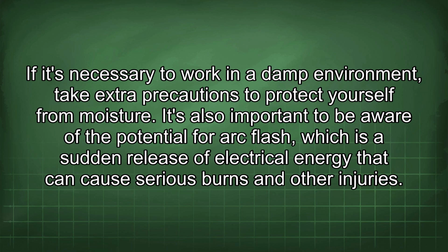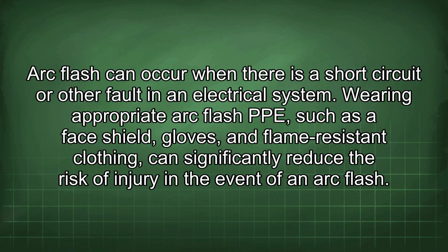It's also important to be aware of the potential for arc flash, which is a sudden release of electrical energy that can cause serious burns and other injuries. Arc flash can occur when there is a short circuit or other fault in an electrical system. Wearing appropriate arc flash PPE, such as a face shield, gloves, and flame-resistant clothing, can significantly reduce the risk of injury in the event of an arc flash.